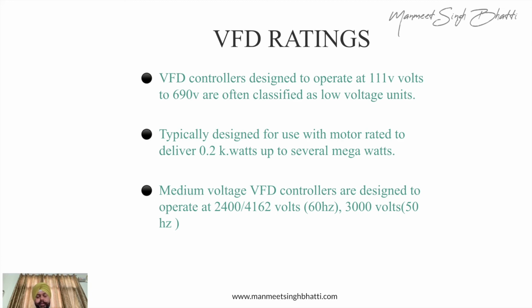Here the voltages are very high. So if you see, we have got 3000 volts, 2400 volts, 4000 volts, 60 hertz and 50 hertz, depending on the country that you are actually employing that thing. So medium voltage is entirely a different subject. We will have a separate discussion based on this medium voltage. And for now, we will be focusing only on the basic LV voltage, that we call 110 volt to 690 volts. So this is the main application for this.